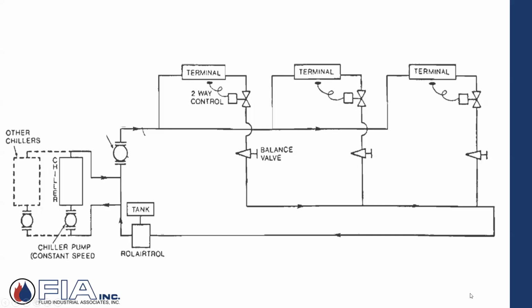And again, before variable speed, it was constant speed. That was the option. You had a constant speed pump that you selected for design conditions, flow and head, and then you had control out to the terminal units, typically a thermostat, space temperature, that would either modulate a valve or open and close, or some mixture thereof. And one of the challenges is, if you were under design load conditions all the time, we wouldn't have this conversation and we wouldn't have variable speed pumping. But the reality is you have design conditions that exist for 2, 3, 4, 5% of the season, whether it be chilled water or heating, and then something less than that. So we have valve operation, valves opening and closing.